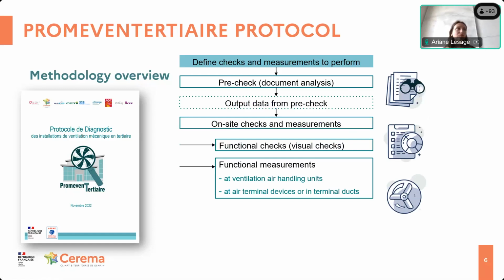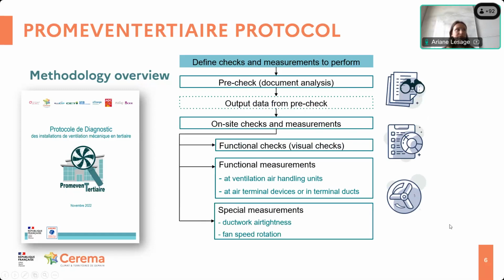The functional measurement can be global and/or local. Global at ventilation air units, with airflow rate, pressure, and fan power measurements, and at air terminal devices or in terminal ducts, airflow rates and pressures can be measured. There are also special measurements, which are ductwork airtightness, as for residential inspection, and fan speed rotation, which is useful in order to avoid fan overload. All measurements and checks are compared to design specifications or regulatory requirements.